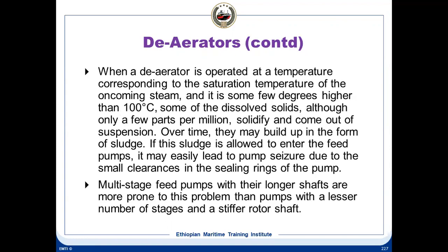When the deaerator is operated at a temperature corresponding to the saturation temperature of the incoming steam, it is a few degrees higher than 100 degrees. So why is it a few degrees? It needs to be a few degrees higher than 100 degrees because boiling point at atmospheric pressure is 100, and here we are maintaining the pressure at marginally above atmospheric. So correspondingly, the boiling point of the water will also increase marginally above 100. And some of the dissolved solids, now there could be some solids.